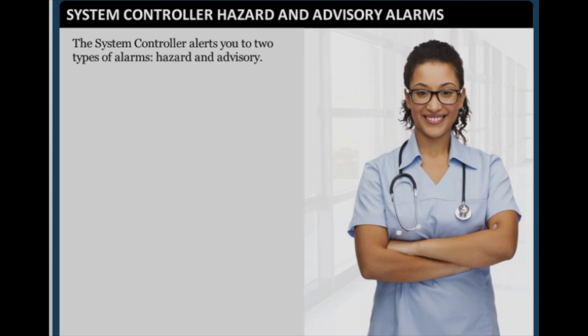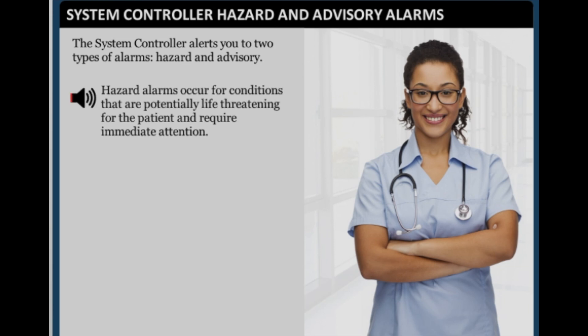The system controller issues two types of alarms: hazard and advisory. Hazard alarms occur for conditions that are potentially life-threatening for the patient and require immediate attention. Advisory alarms are important but not life-threatening. When an alarm occurs, messages appear on the system controller user interface screen to help resolve the problem. These screen messages indicate the alarm type and the action required to resolve the alarm.